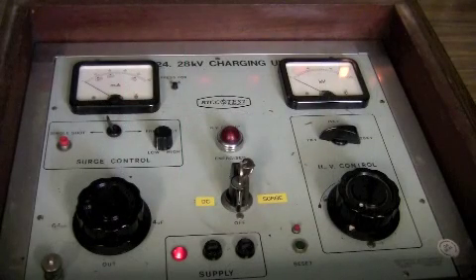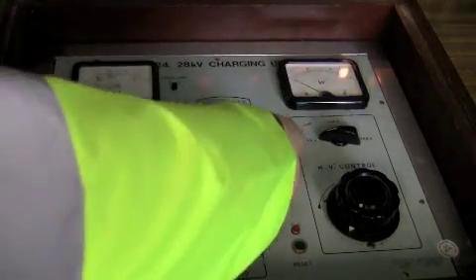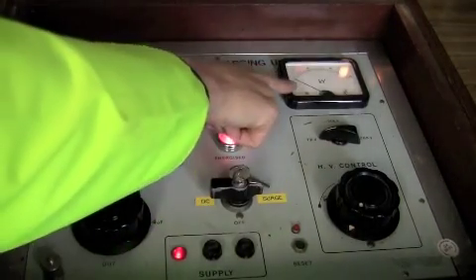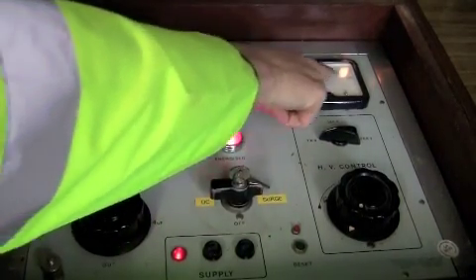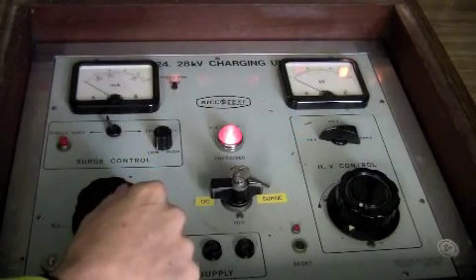Having pre-located the fault, we're now going to carry out a pinpoint location using an acoustic method with this capacitor discharge set. I'm going to switch the set to surge and over here I have my meter for kilovolts. This one reads up to 30,000 volts. I've only got it set to 7 kV maximum though.